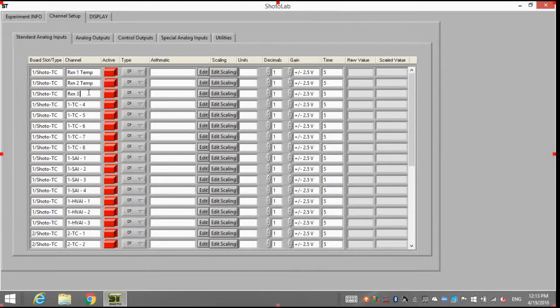The first reactor is temp 1, the second reactor is temp 2, the third reactor is temp 3, and the fourth reactor is temp 4. I also installed a thermocouple for ambient temperature reading, and I'm going to input that as well. Next, select the type of thermocouple you are using. These are all type Ks. For me, it's easier and faster to work from top to bottom.